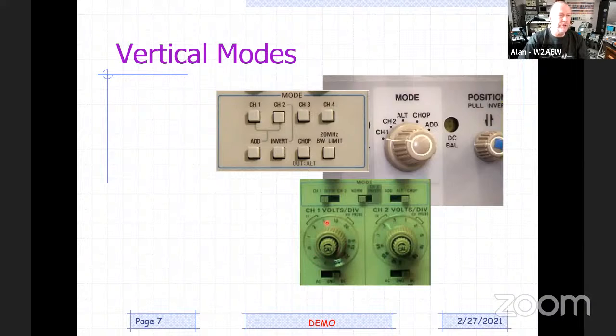Typically on the volts per division, you'll see a center concentric knob that says CAL with a clockwise turning arrow. If you turn that cal knob all the way to the right, it'll click, and in that clicked position you're at the calibrated number of volts per division. You do have the option of turning it to the left for a kind of vernier adjustment. So if you wanted to make the waveform on the screen a given size, like maximize it, and you didn't care about the actual volts per division, you could use the variable for that. It can also be used for things like some rise time measurements, but most of the time you're going to leave this fully clockwise in its clicked, detented position to get the calibrated volts per division. I meant to mention that on the previous slide.